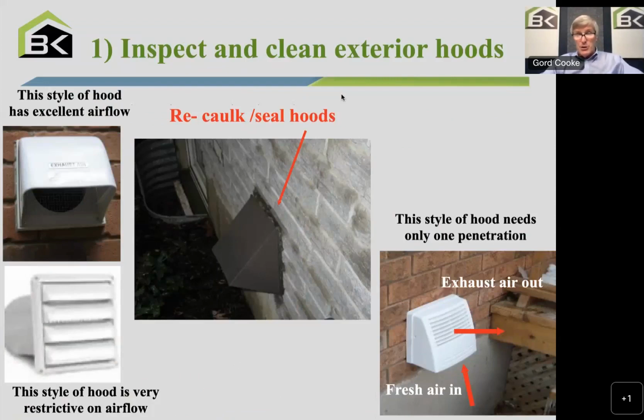On the bottom right, sometimes you go, I only see one hood. Well, it might be what we call a tandem hood or a combined hood. And 2 or 3 of the manufacturers have these. They work really well. What they're doing is they're concentric. Air's brought in the bottom of the hood. The exhaust air is expelled out through the front. And again, they just need to be checked. So on some houses, you might find only one hood instead of 2. And then in the middle, I'm suggesting just check if the hoods are still thoroughly sealed, thoroughly caulked. And every now and again, every 7 to 10 years, you might have to recaulk the hood.